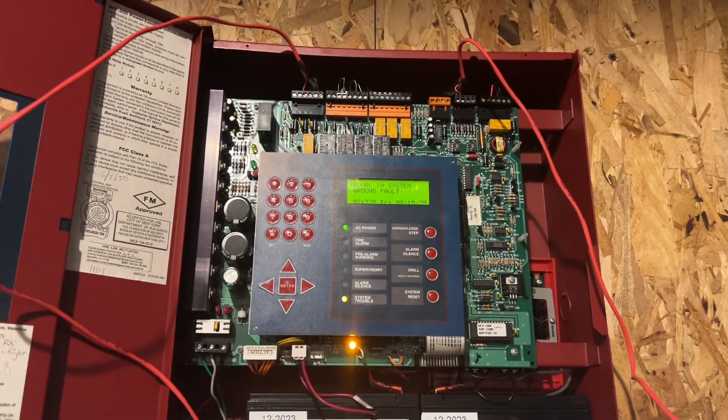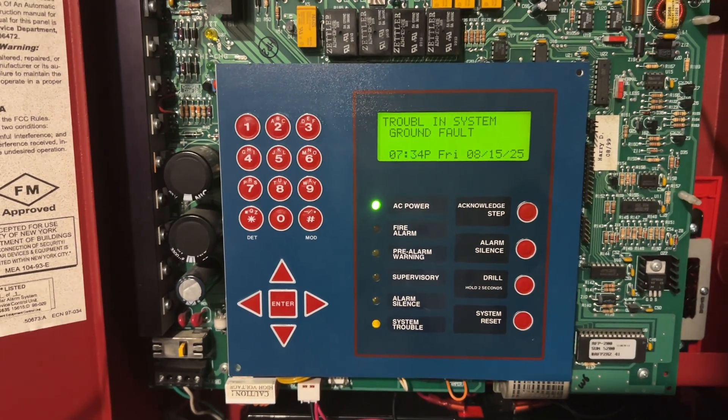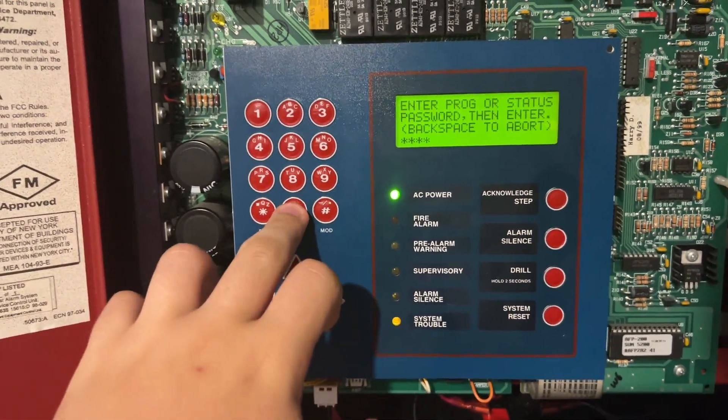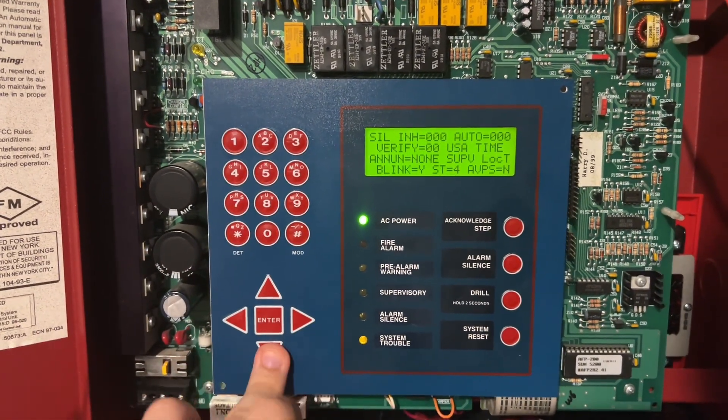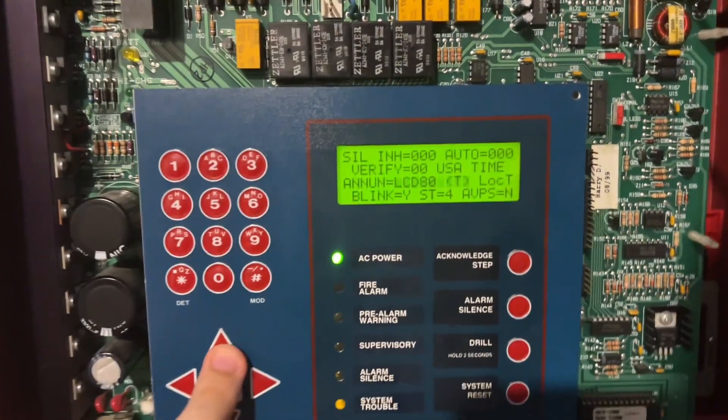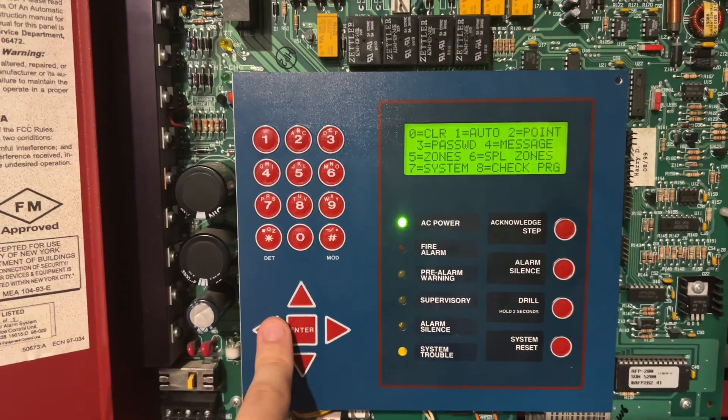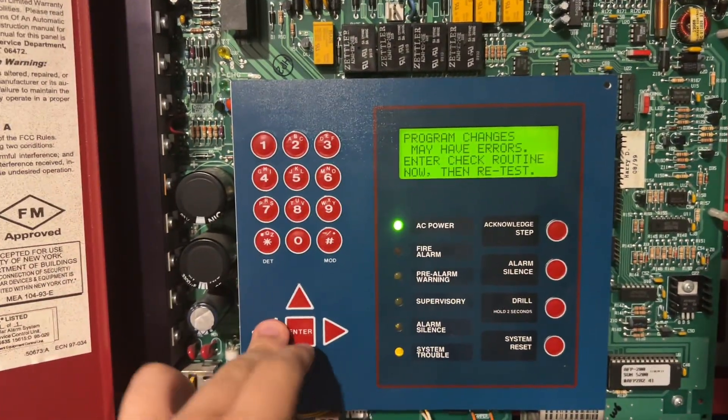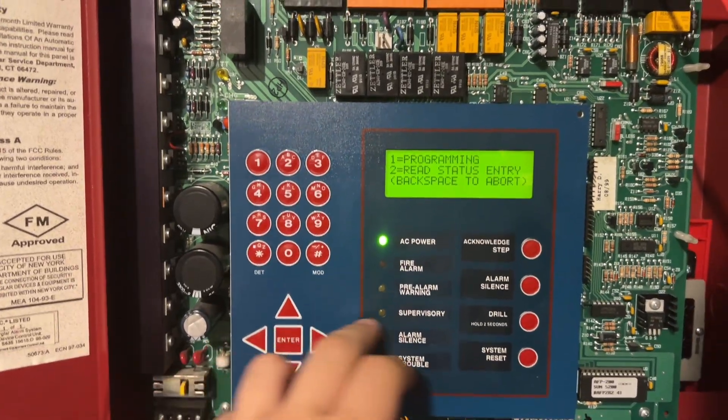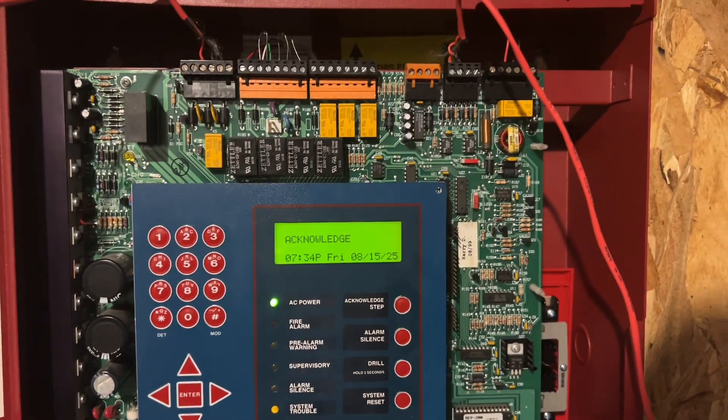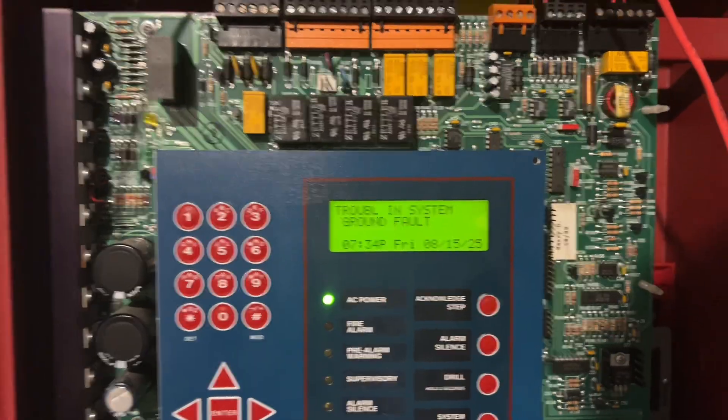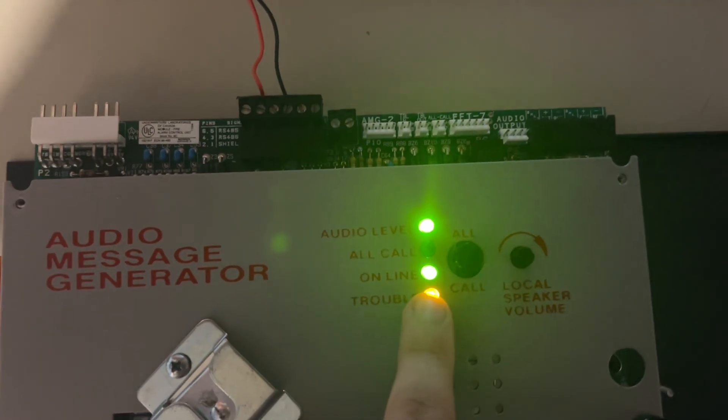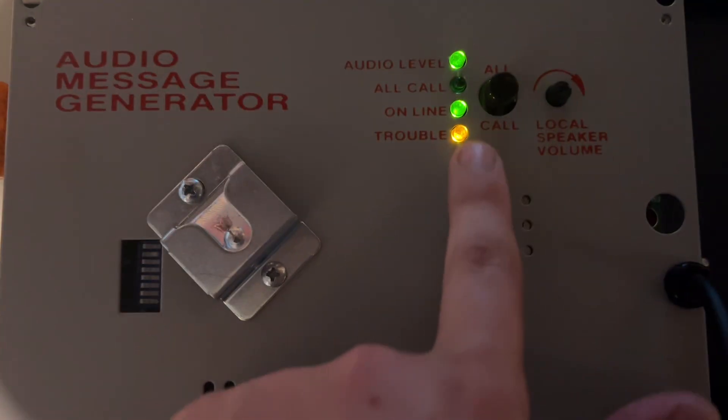But now let's get it to communicate with the panel. Now, in order to get the AMG to actually work, we need to enable the serial bus. So, I'm going to tell the panel that it has one enunciator, ACS address 1. So, now the panel has the serial bus enabled. It says enunciator 1, no answer because this is not set to address 1. I don't know what address it is, but you can see it is communicating because it says online.